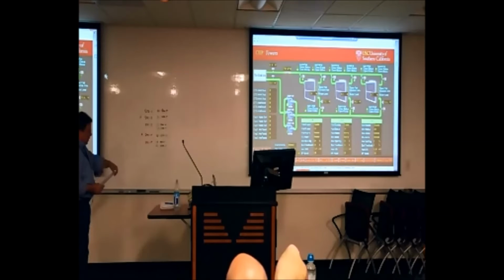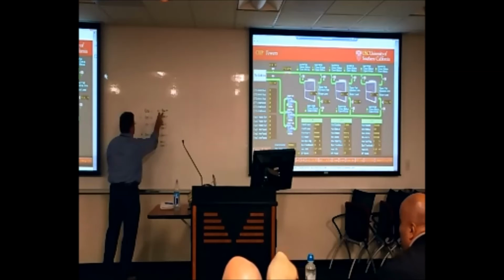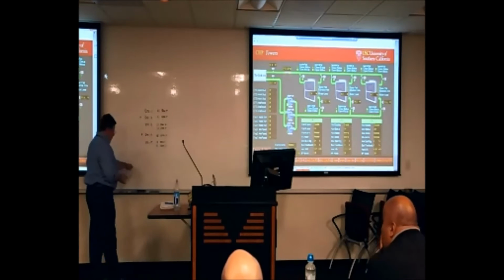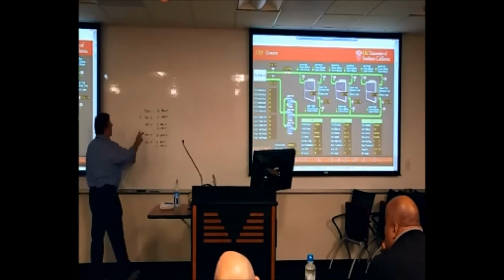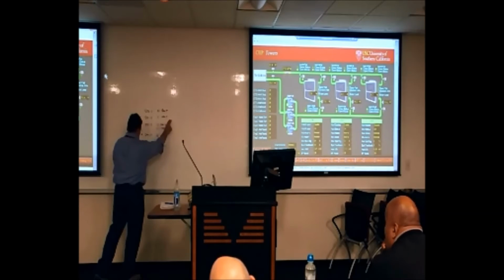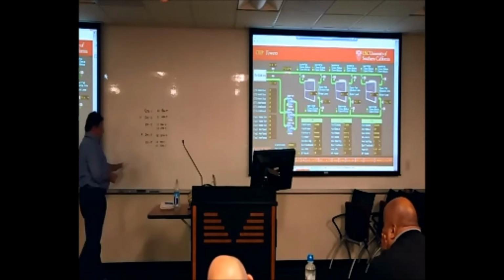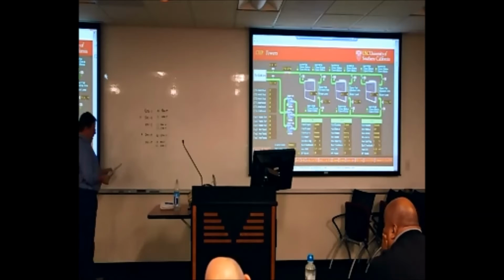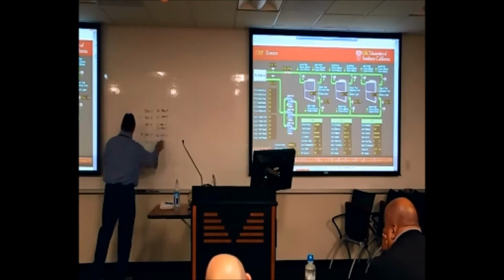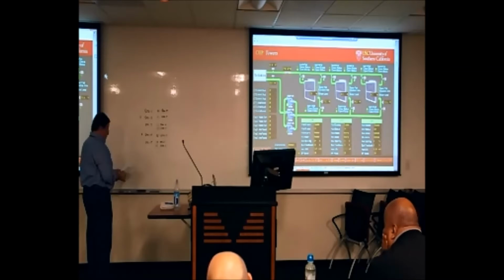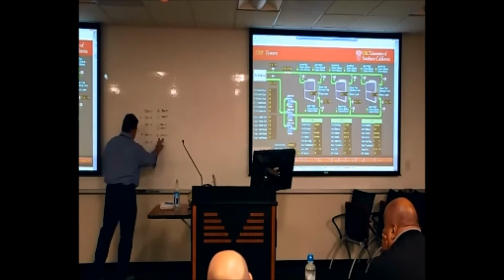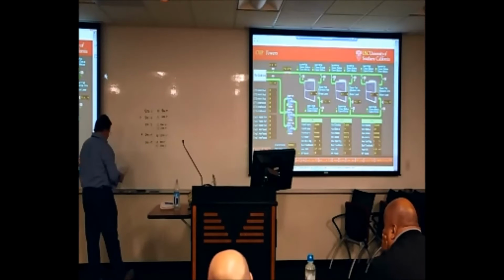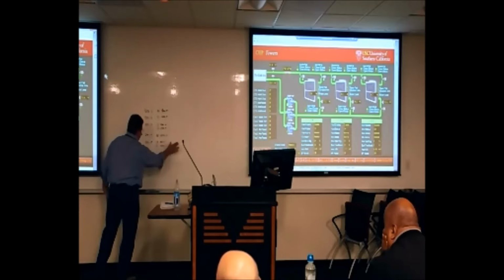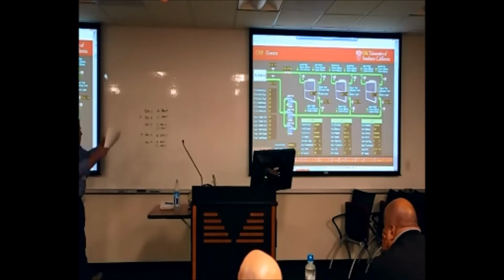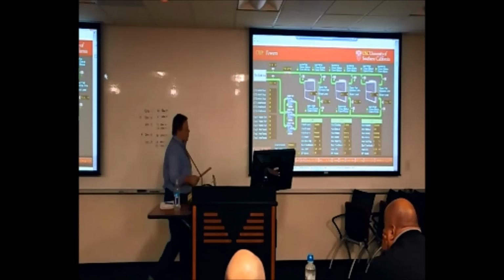And real quick, the definition of stage 1: the 800-ton chiller is 1 cooling tower, 1 condenser water pump. Stage 2, the 1,500-ton chiller, is 1 condenser water pump and 2 cooling towers. Stage 3 is going to be 2 cooling towers, 2 condenser water pumps. Stage 4, which is the 2 1,500-ton, is going to be 2 condenser water pumps and 3 cooling towers. And then stage 5 is going to be all up again, the 3 pumps and the 3 towers operating. So that's how the sequencing takes place in terms of the number of towers we're being asked for right now.